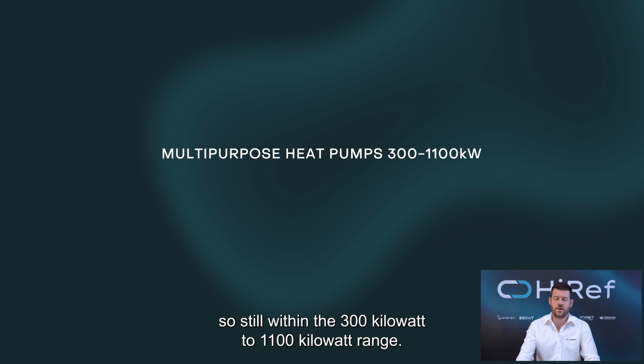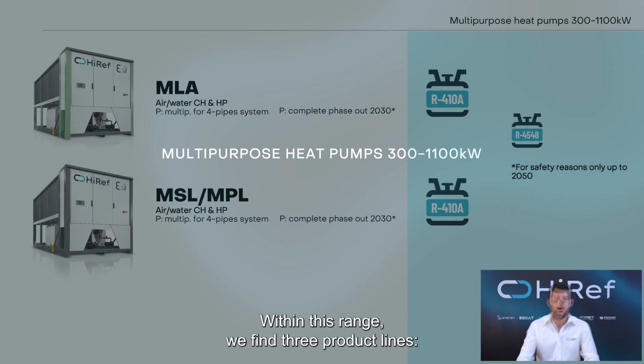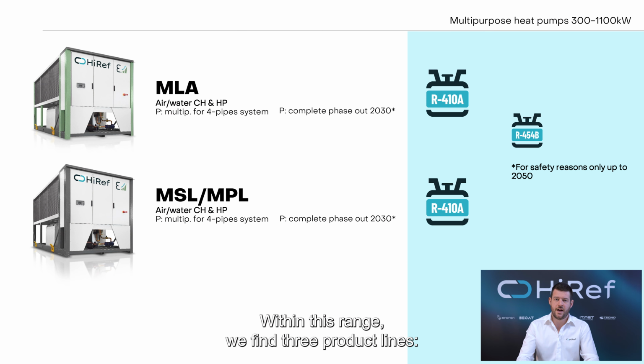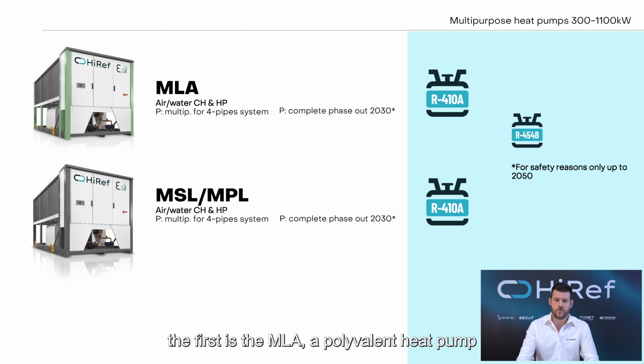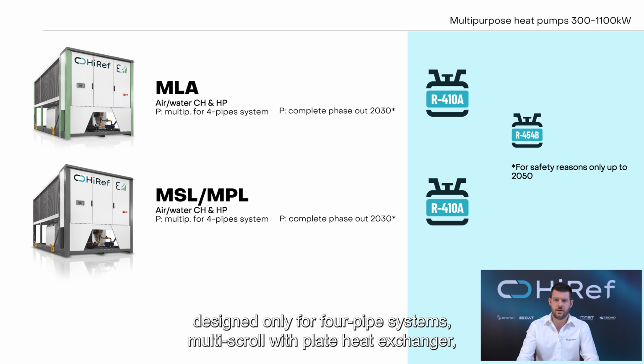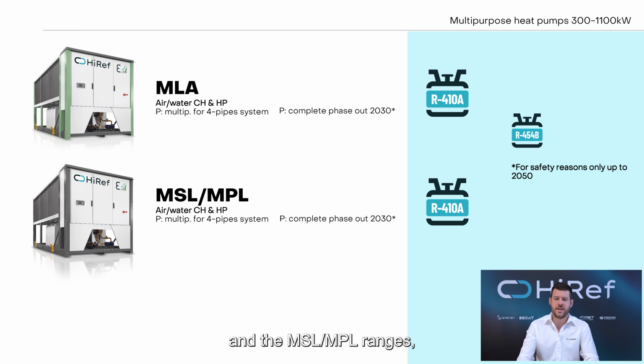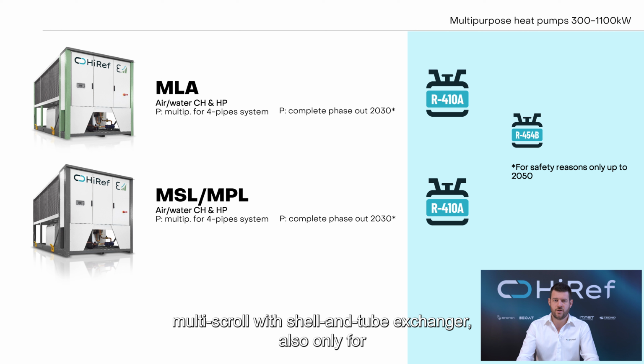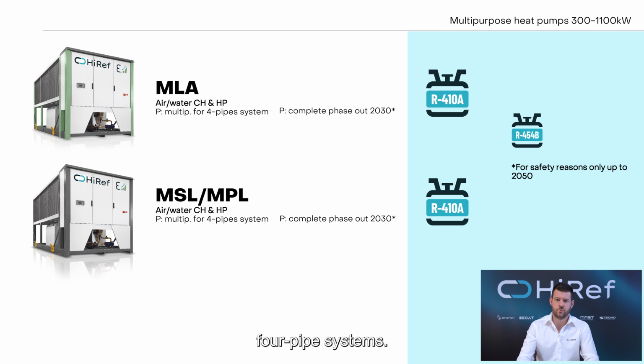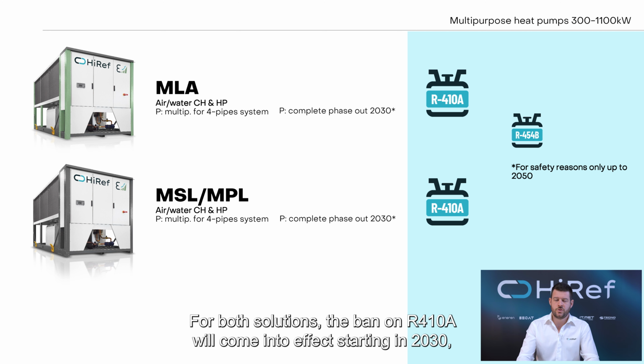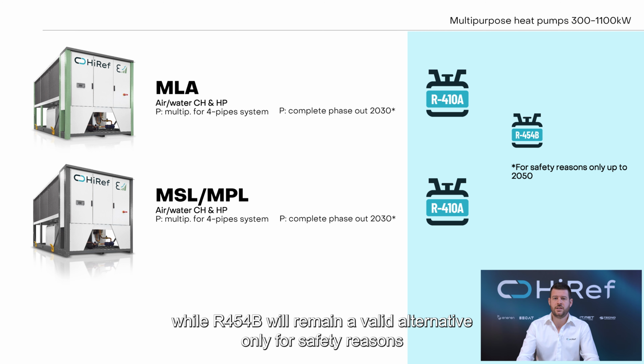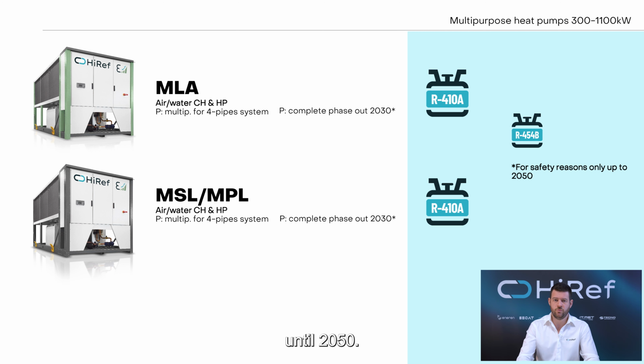So, still within the 300 kilowatt to 1.1 megawatt range. With this range, we will find three product lines. The first is the MLA, a polyvalent heat pump, designed only for 4-pipe system, multi-scroll with plated exchanger, and the MSL or MPL range, multi-scroll with the shell and tube heat exchanger, also for only 4-pipe system. For both solutions, the ban of R-410A will come into effect starting in 2030, while 454B will remain a valid alternative only for safety reasons until 2050.